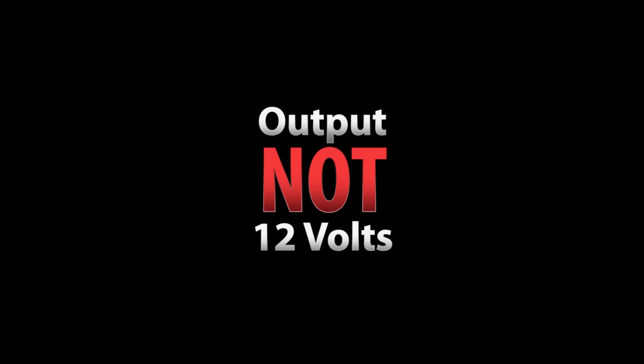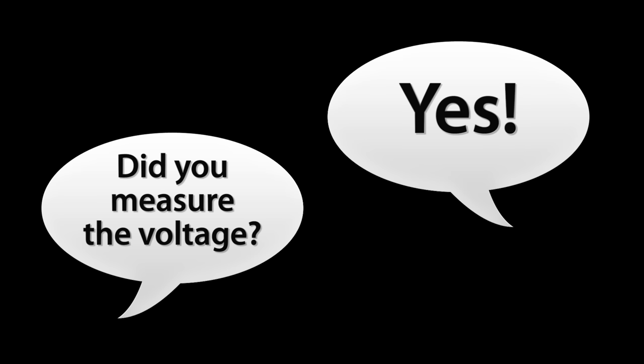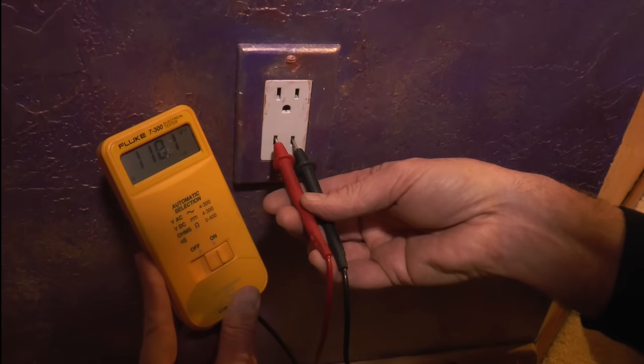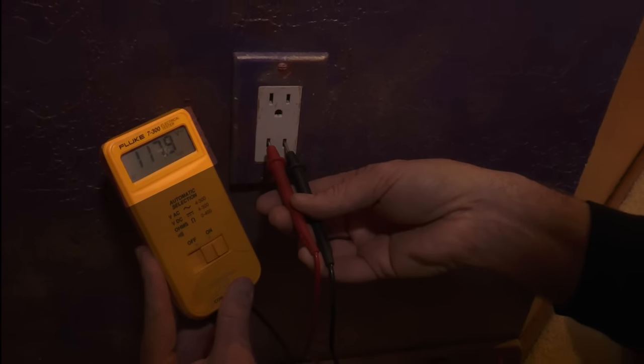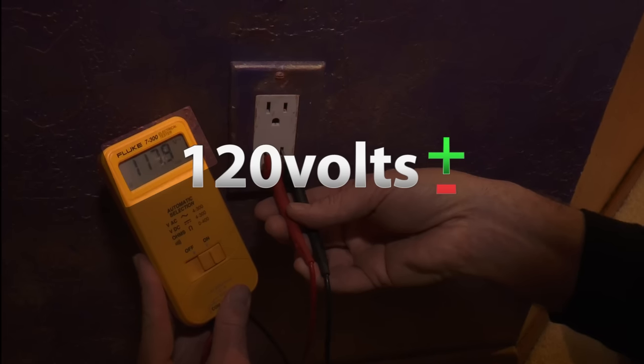The second complaint we get is that the output is not 12 volts. I always ask the customer the input voltage they are using. I always get the same answer, 120 volts. When I asked if they measured it, they always tell me yes. Well, I hate to tell you, you almost never have 120 volts. And if you do, it varies during the day.